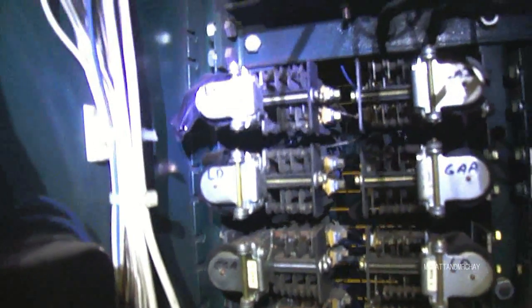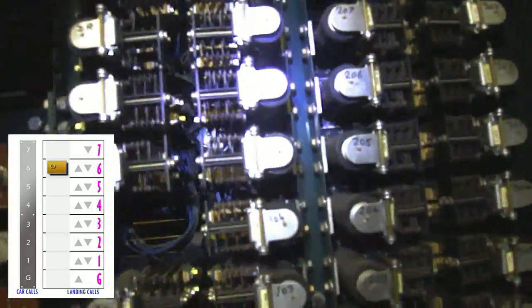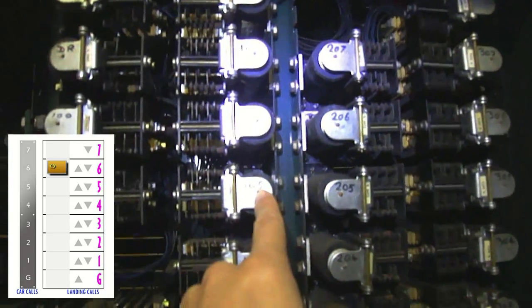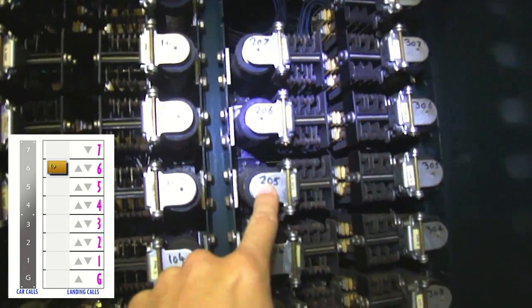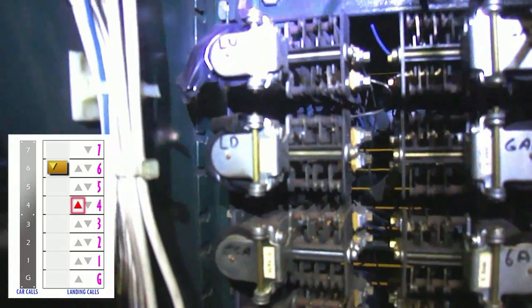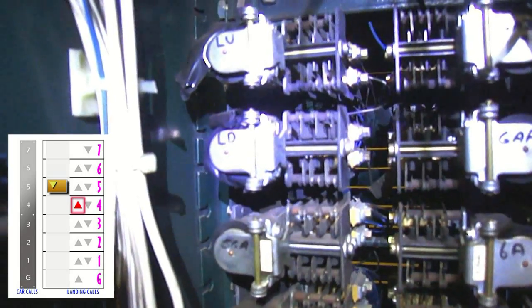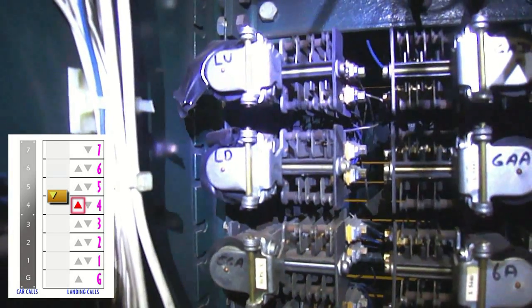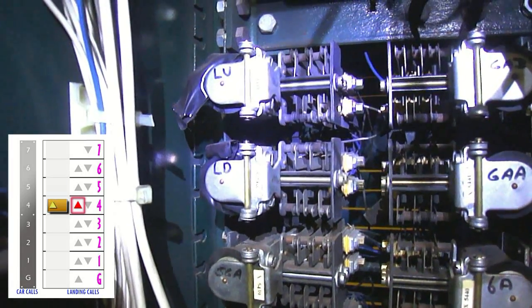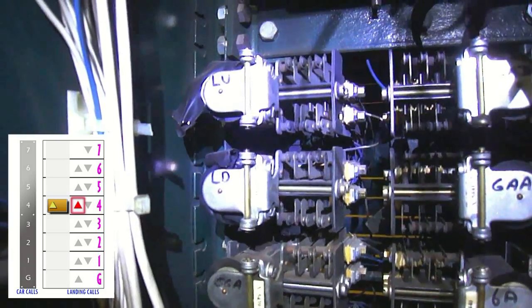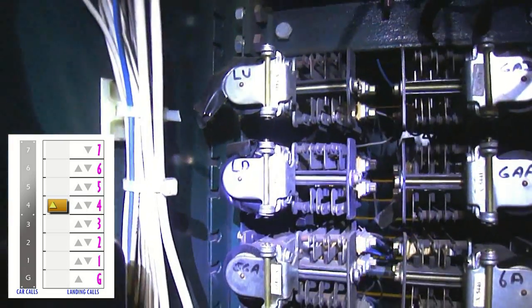Let's try out these levelling up and levelling down relays, LU and LD. Where did I leave the lift? The lift is on the sixth floor. So I'm going to give it a call a few floors down from where it is now. Let's give it an up button on the landing. And the levelling down relay is now on. Did you see levelling up come on at the same time then?